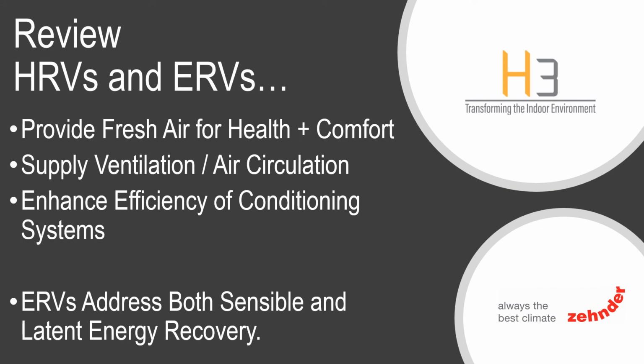To review, HRVs and ERVs do not provide heating and cooling. They provide balanced, filtered, fresh air ventilation while conserving the energy of heating and cooling within the home. When installed properly, these devices conserve more energy than they use. ERVs conserve both sensible and latent energy recovery.